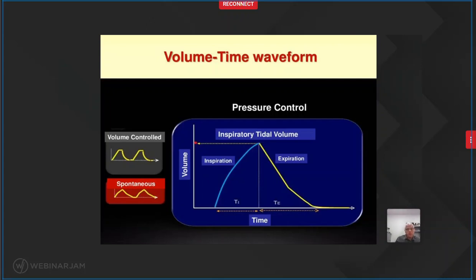Okay? And as you can see here on the left side, during volume control, usually you get a small plateau because that's the parameter that the ventilator is using. And during spontaneous breathing and pressure support it is more pointy because you don't usually have a plateau in volume unless your inspiratory time is too long.